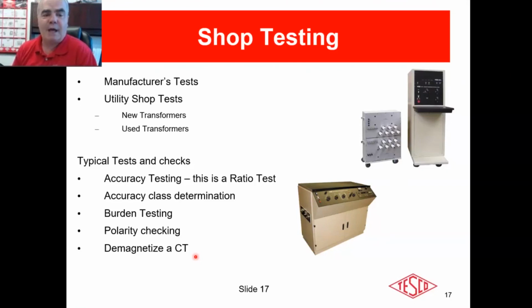And if you do that, you'll never notice that there was a problem because it was, quote, always that way. The bill never changed. There was no radical difference in the way the service performed and was metered. All right. So demagnetizing them on the way out, if no other reason, that should give you a reason to test all your transformers before they head out the door.